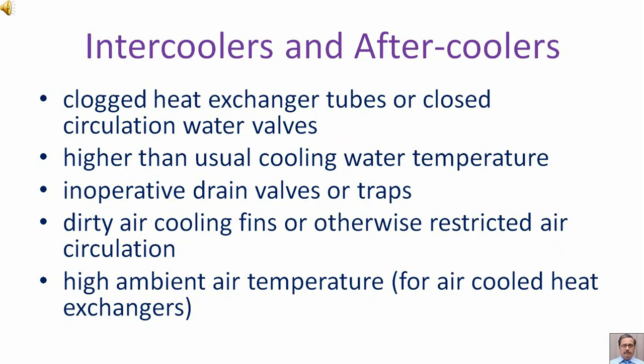Causes of abnormal discharge include: clogged heat exchanger tubes or closed circulation water valves, higher than usual cooling water temperature, inoperative drain valves or traps, dirty air cooling fins or otherwise restricted air circulation, and high ambient air temperature for air cooled heat exchangers.